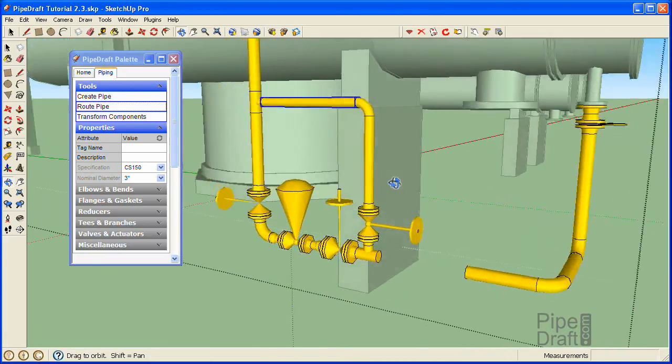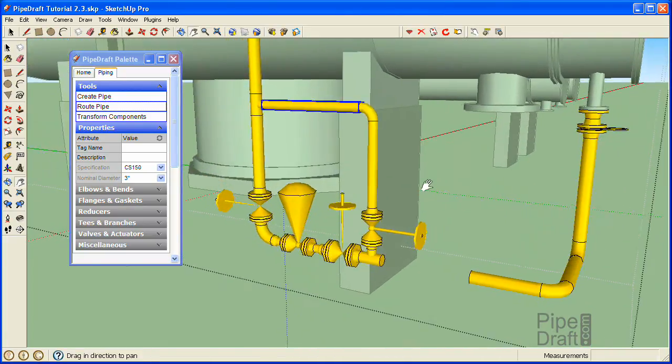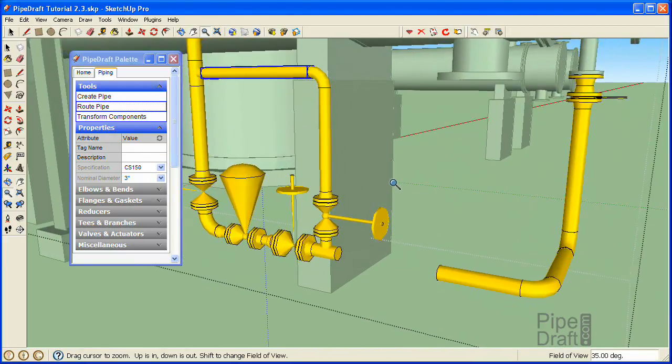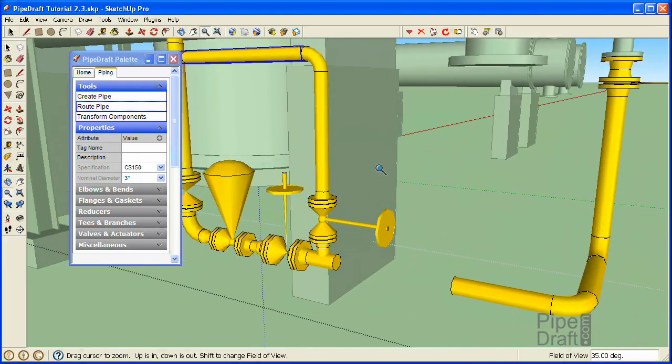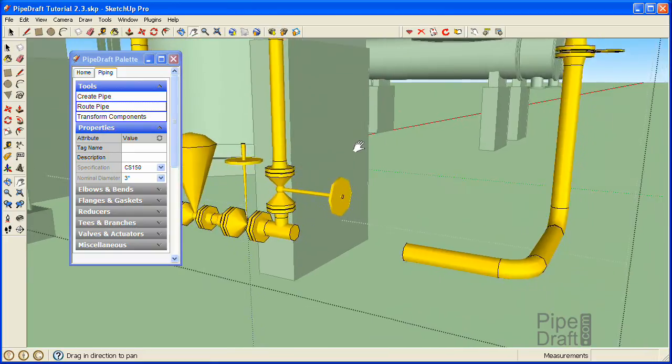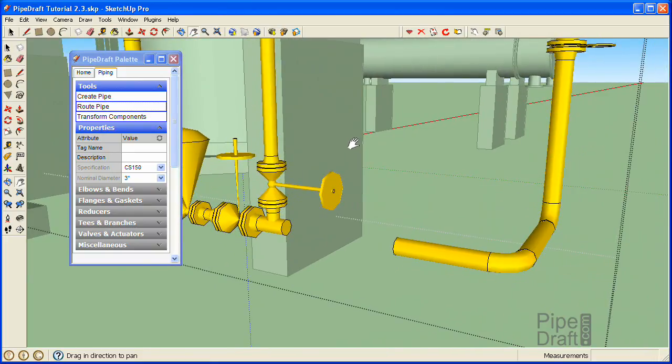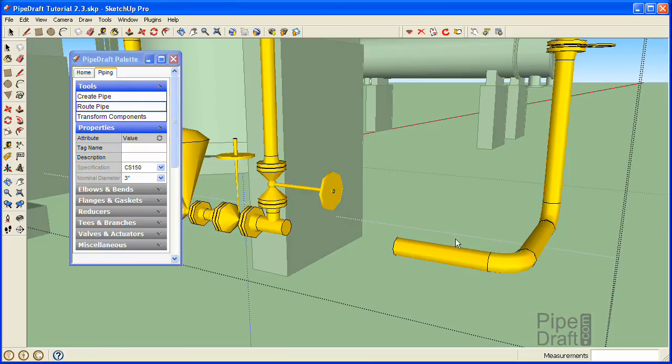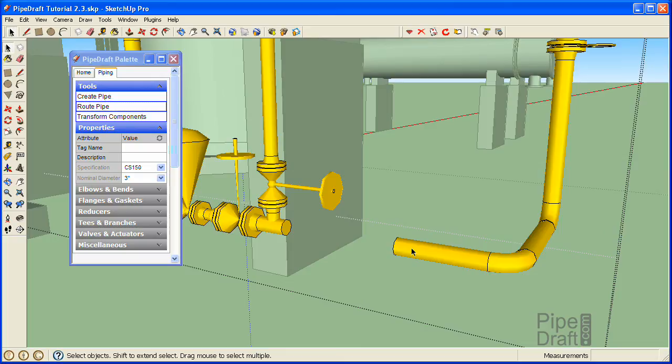We could simply close up the gap in our 4 inch pipeline, but we think we can make one more improvement in our layout. When this end of the reboiler needs maintenance work, this horizontal elbow and these two pipe segments may tend to get in the way somewhat. We think we could improve this situation and also conserve a little more piping material if we reroute the horizontal pipe at a 45 degree angle. First, let's delete the fitting components we don't need.